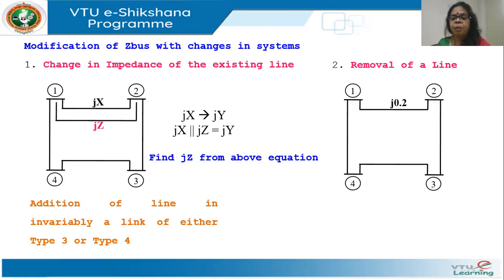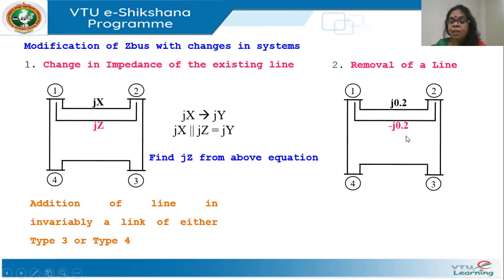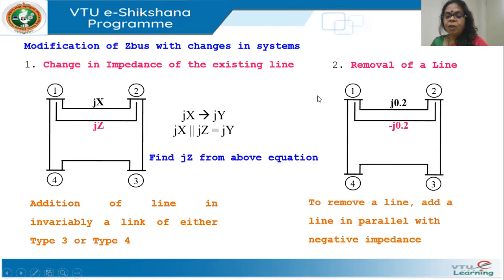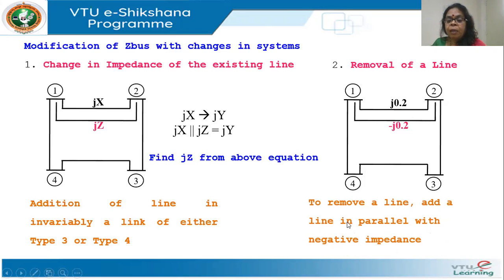If a line is removed — say a line of impedance j0.2 — I simply add another line in parallel with negative impedance minus j0.2, so the net admittance becomes zero and that line's effect is cancelled. So to remove a line: add a line in parallel with negative impedance, because the net admittance will become zero, modelling the removal of the line.